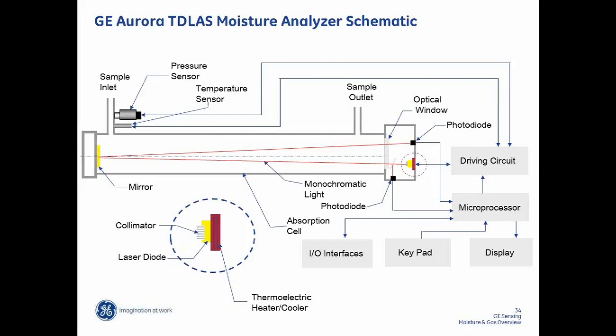So as the laser is tuned or ramped through a narrow band frequency in the infrared, there's a particular frequency where water absorbs the energy. The water molecule has a unique vibrational and rotational characteristic that absorbs that photonic energy. So you're getting, at that particular frequency, fewer photons than what you put into the system. And the longer the path length, the more absorption or loss of signal you'll get if there's water in it. So by having a constant length, we're able to look at the absorption characteristic and determine that, yes, there's water in there, but not only that, how much water, by looking at the loss of signal or the absorption.